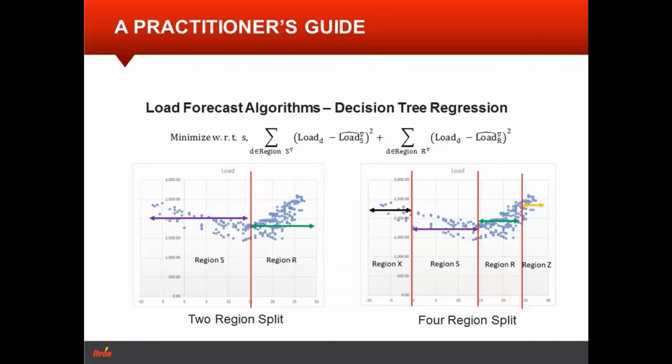and we say, bam, that average is what we're going to forecast with. But knowing how to segment your data, whether you segment by weekdays versus weekends or Mondays versus Fridays, and whether you're segmenting between hot days versus cold days, that knowledge is rooted in your similar day algorithm. The decision tree just takes that knowledge and implements it more easily in terms of a computer algorithm. But at the core, you need to have that deep knowledge about how loads vary and what circumstances you want to segment your data on.